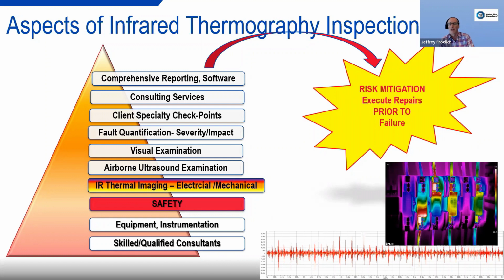The rubber hits the road with the reporting. With the technology and tablet software, we have the ability to produce very high resolution reports with amazing graphics and root cause, probable cause, recommendations, checkpoints, pinpoint the asset, throw on our severity and impacts. And ultimately, your company wants to be prepared to quickly mitigate those risks. The only way you get that done is get it out to your maintenance and engineering teams and have them do a local de-energization, complete the repair safely, and then fire the equipment back up, and you're back up and running. Therefore, you're in a controlled mode versus a reactive emergency mode. So that's pretty much an overview of the inspection.